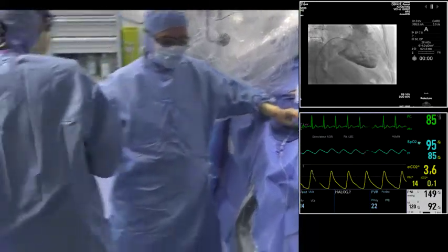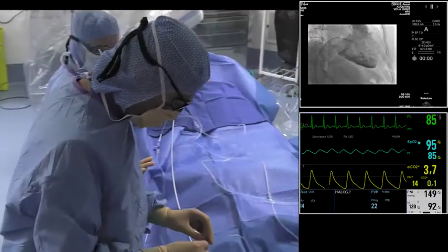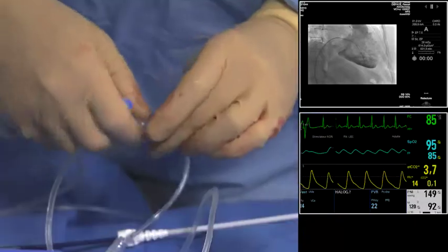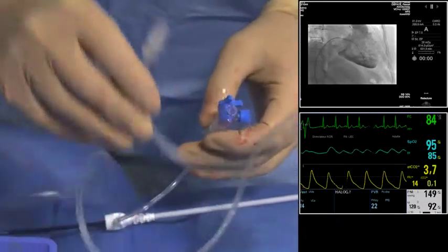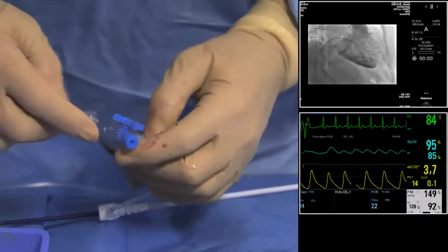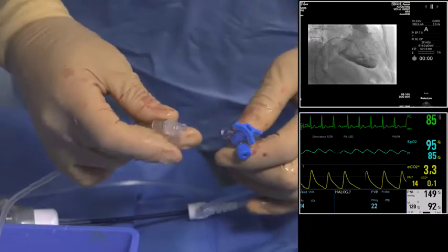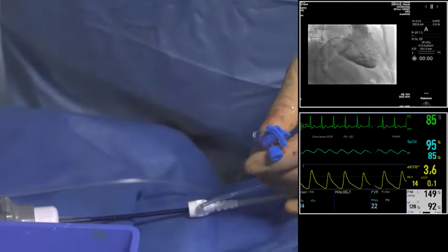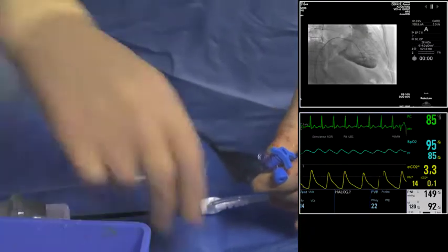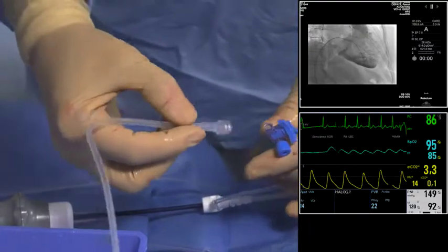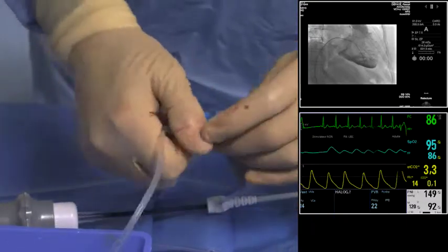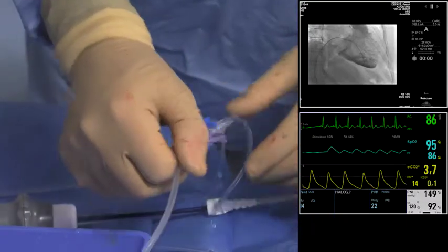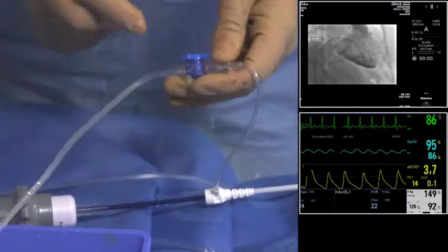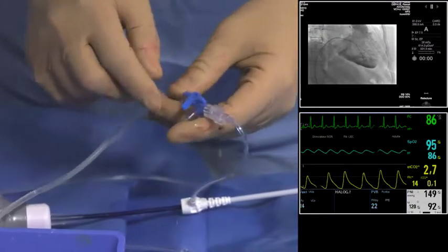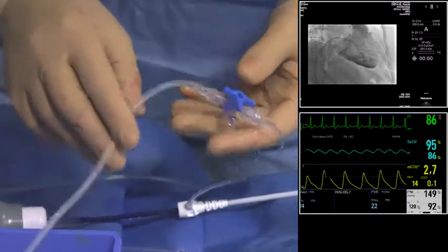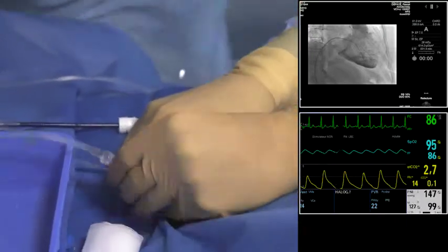between the protective sleeve and the high pressure. This is on the delivery sheath. The other, okay, this one. And the last one is on the handle. The three-way introducer, the three-way cock, is for the syringes, for the injection of dye.